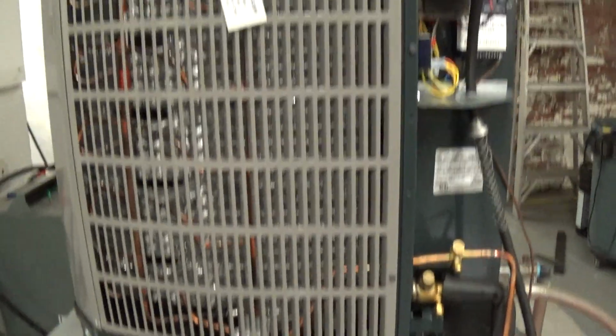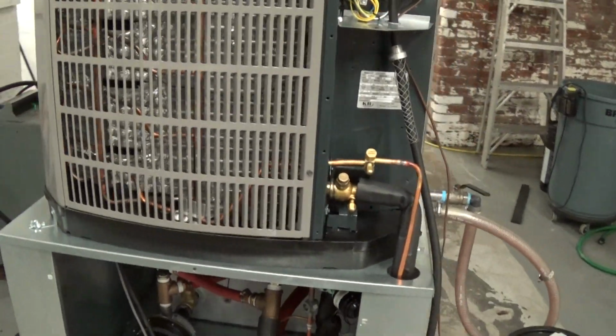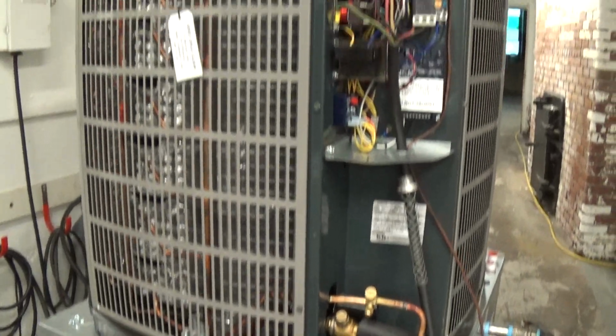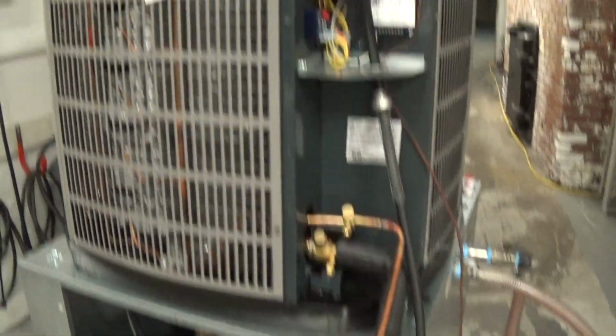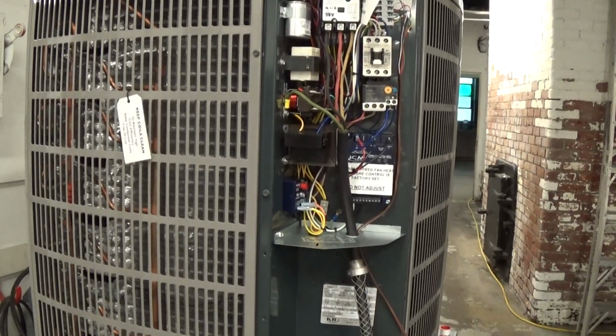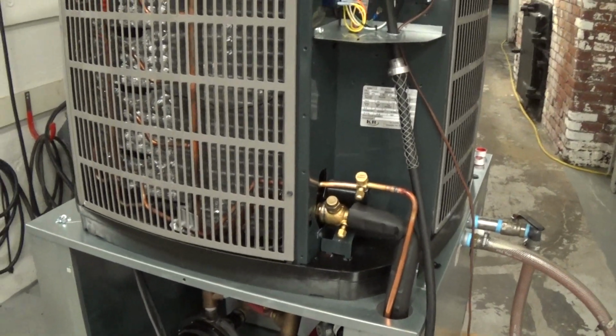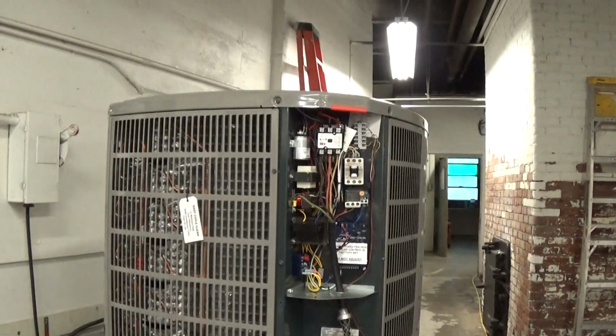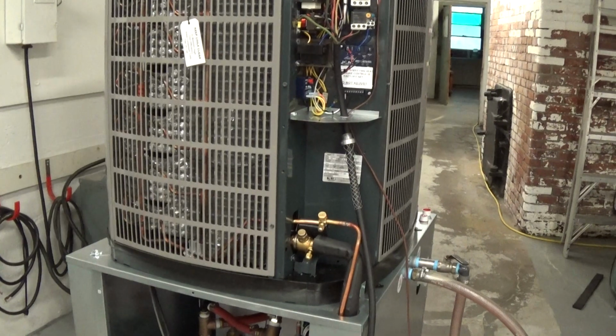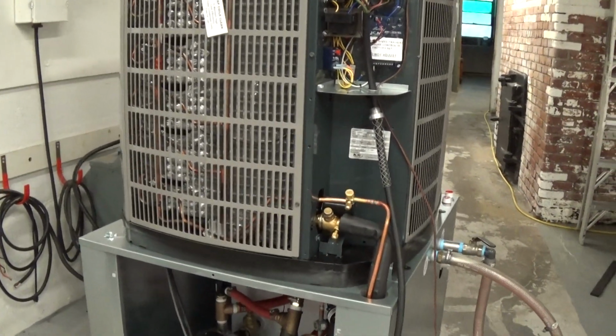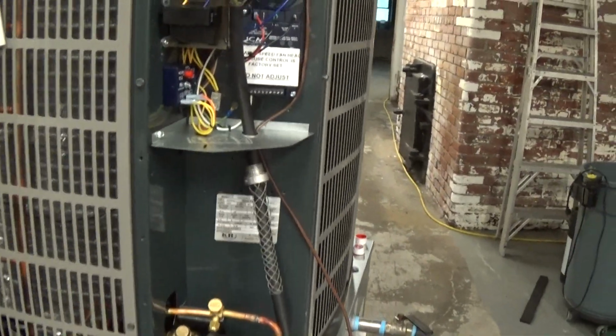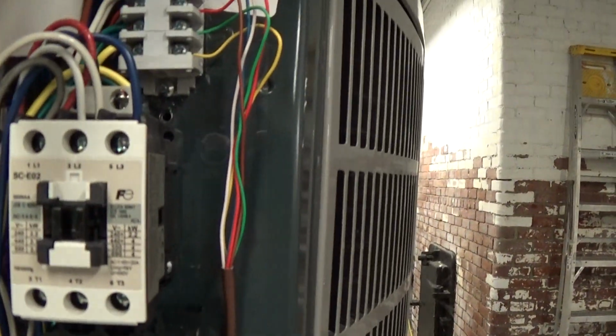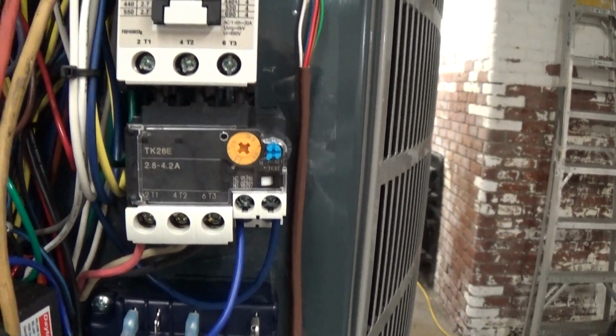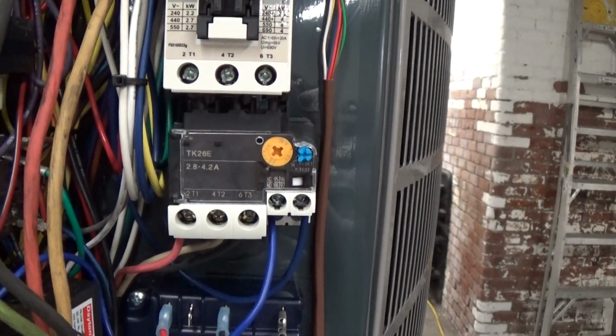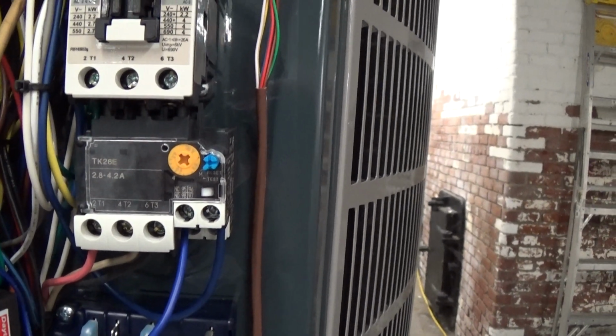The unit has a high and low safety refrigerant switch. If those are tripped, we shut down all power. I'm sorry, we don't shut down all power. We shut down just the refrigeration circuit. So the controller will still be on. The symptom will basically be that the unit's not chilling. So again, that's the high and low refrigeration safety circuit. The pump contactor is here. That's something that can trip if it's overloaded. Overload is mainly due if there's not enough back pressure on the water piping or the glycol piping circuit.